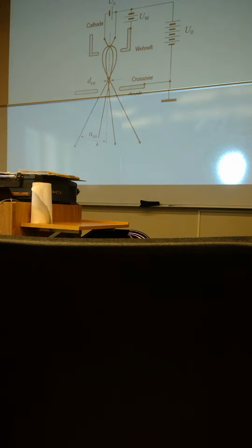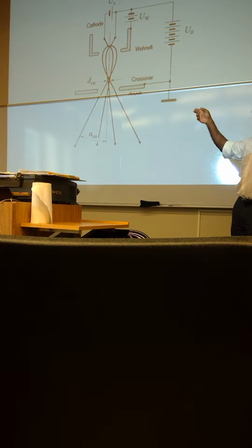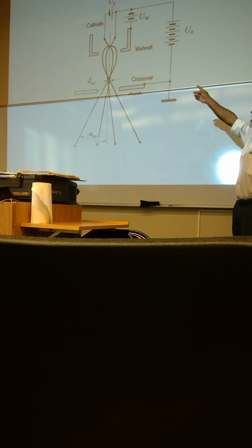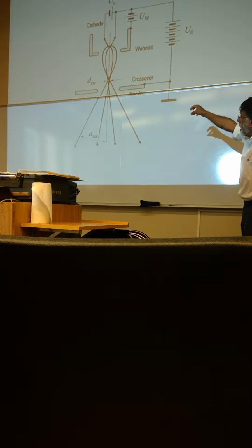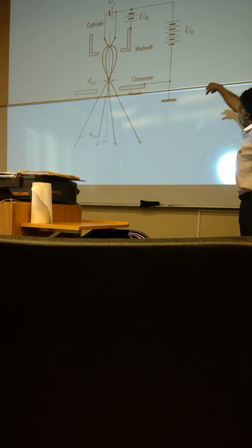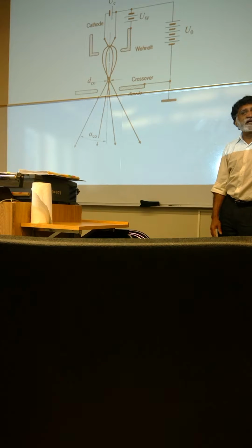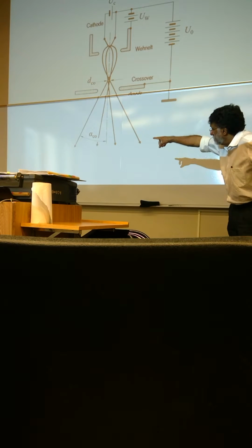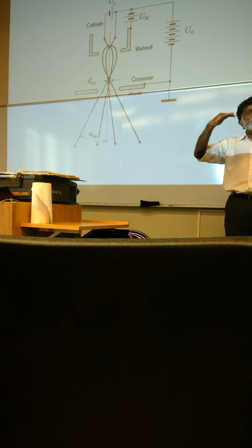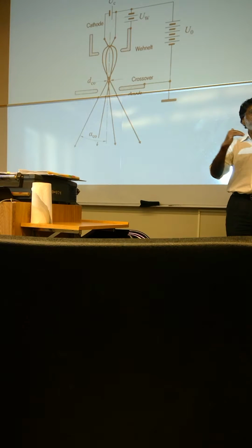In terms of components, we have already seen the gun. We discussed the gun when we talked about sources and probes. Basically, you have a cathode, there is a small potential applied, the current comes out of the cathode, and then here's the anode with the high potential, which is in this case somewhere between 5 and 30 kiloelectron volts, typically. Then it comes out, there is this divergence angle, and that is controlled by the apertures to make sure that the angular divergence is controlled.